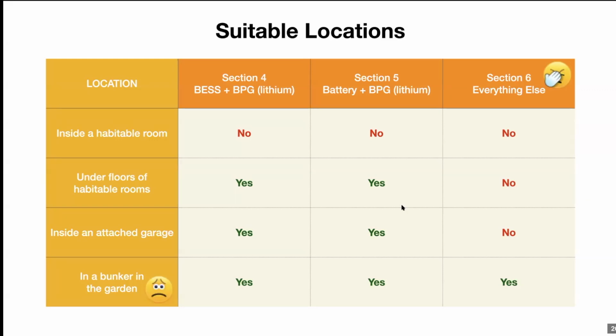It's specified in the standard that it can be cement block, brick, concrete, terracotta tiles, or cement sheeting, or any product that complies with AS/NZS 1530 Part 1, I think it is, which is a fire standard for the protection against the spread of fire. And that's a very tough standard to meet, by the way. I tried to find some products that met 1530 and I couldn't find many. Ironically, even cement sheeting doesn't meet it, but we're allowing cement sheeting. So what I'm seeing already in Australia is people are using cement sheet as that fire barrier.